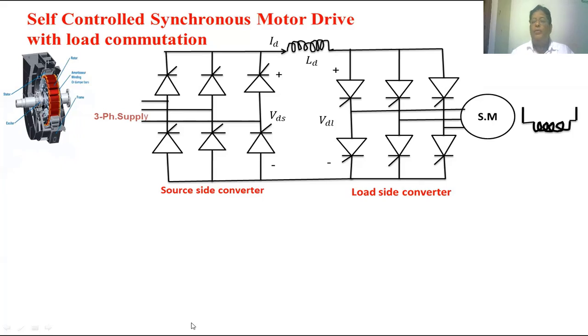Now, if we want to apply regenerative braking for the synchronous motor, the load side converter will be operated as a rectifier, so the firing angle of this converter becomes less than 90 degrees. The source side converter will be operated as an inverter. Whatever power is given by the synchronous motor that is available to the DC link will again be given back to the supply. In this manner we can apply regenerative braking for the synchronous motor.